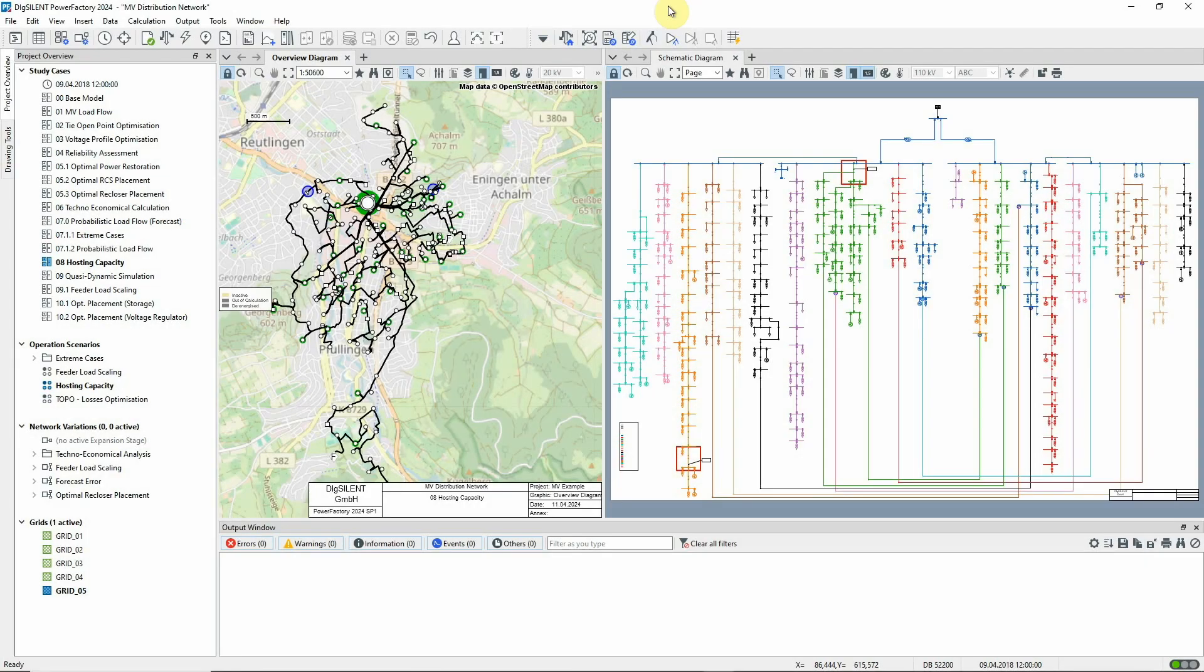In this video, we will demonstrate the use of hosting capacity analysis in the MV distribution network. This analysis is used to determine the maximum additional load, or DER, that is distributed energy resource, that can be connected at a node without violating system constraints and without the need for network developments.